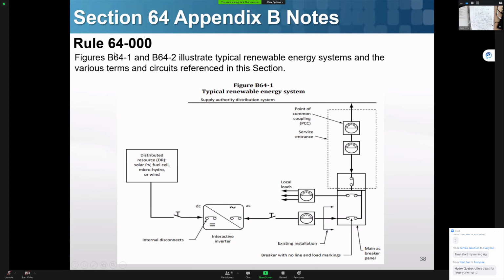So here, I think in Appendix B, they show you a typical renewable energy system. You can see here the supply authority, in this case BC Hydro's. And we have the distributed resource: solar panel, fuel cell, micro hydro, hydrokinetic, or wind power. We have a disconnect means down here, and you could be feeding DC or AC, depending. If you have photovoltaic, you will feed in DC. If you have a micro hydro or wind turbine, you feed in AC. Then you might have an interactive type of inverter to connect onto the hydro side. But the hydro side is always AC. You also need a disconnect down here.